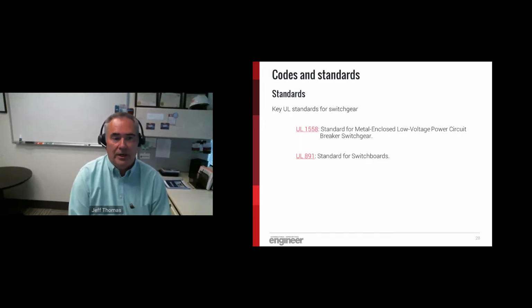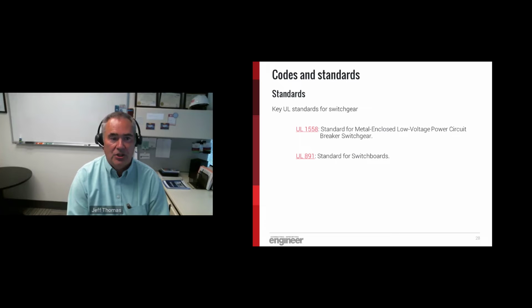John mentioned UL 489 for breakers. There are also some key standards for switchgear. 1558 governs metal enclosed low voltage power circuit breakers, and 891 talks about standards for switchboards. And these will all be taken into consideration by the design professionals as they're designing the installation.